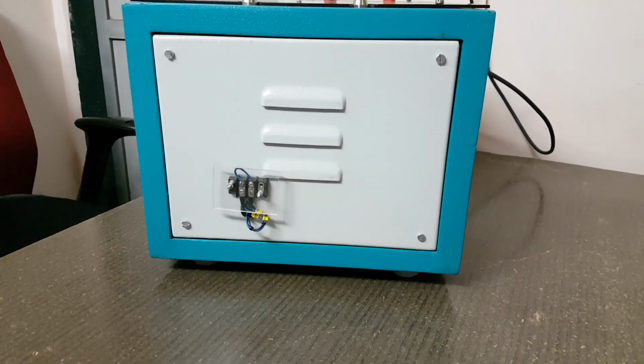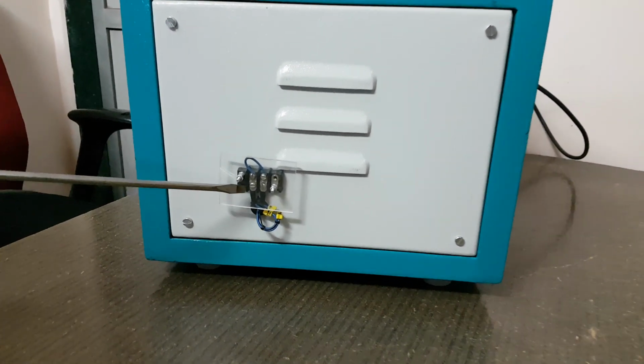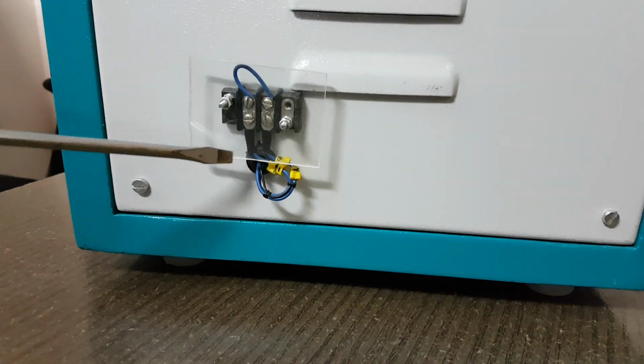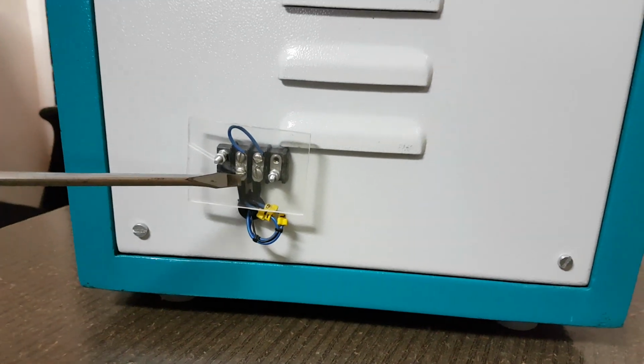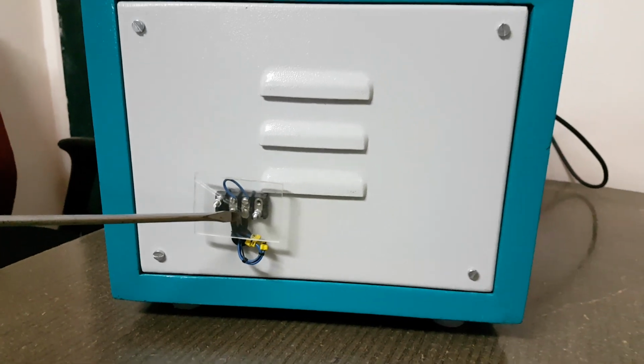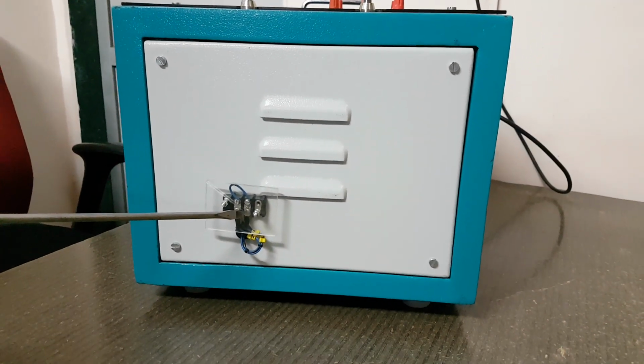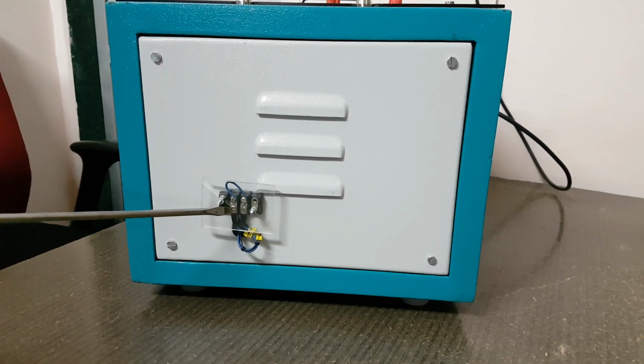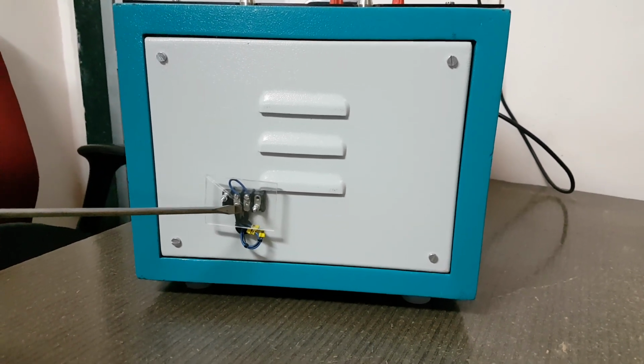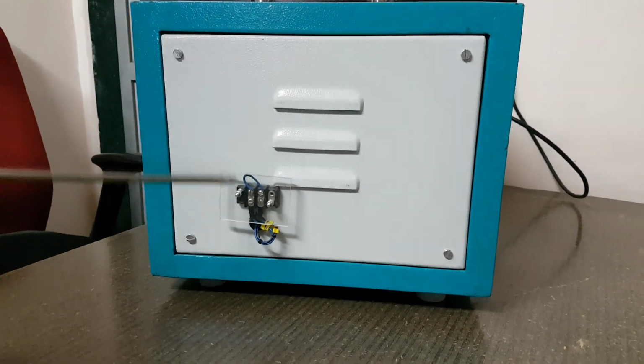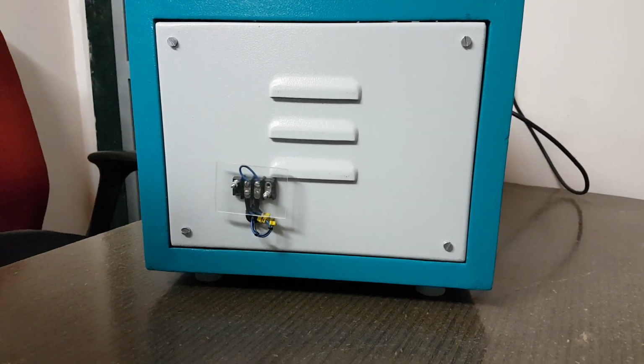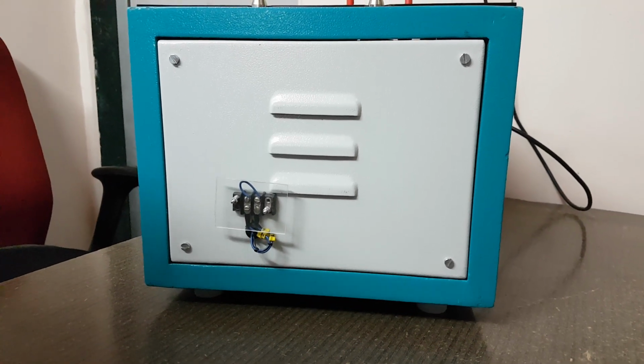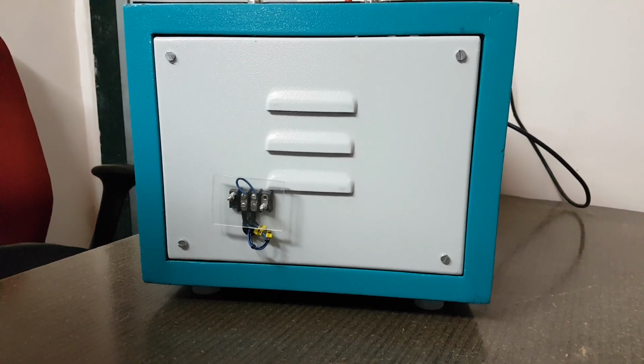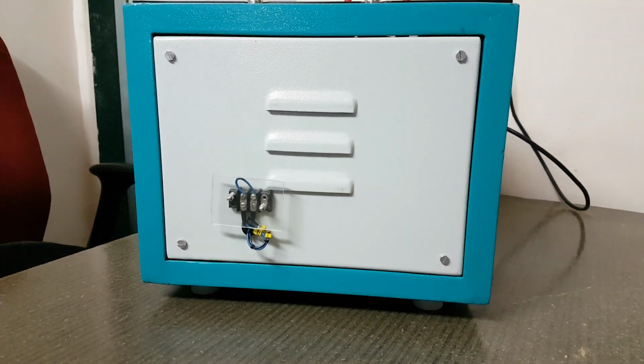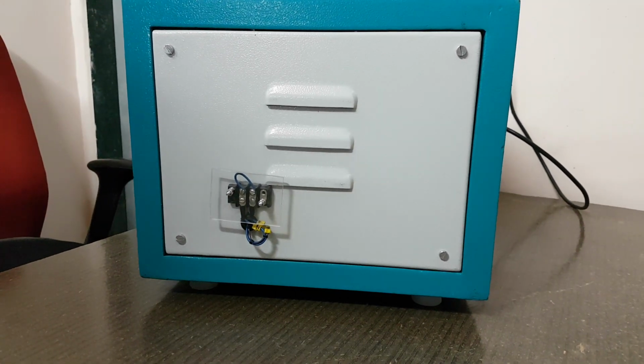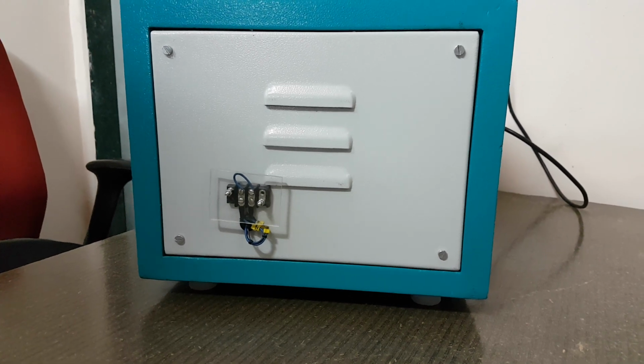This is the right side panel of the instrument. Here you will see there are two terminals with wires. These two terminals are provided as a chamber door interlock. We can interlock the high voltage testing with the high voltage chamber door with a limit switch. These two wires can be connected to the limit switch fixed at the chamber door so that the instrument will only work when the chamber door is closed. This is called the chamber door interlock.